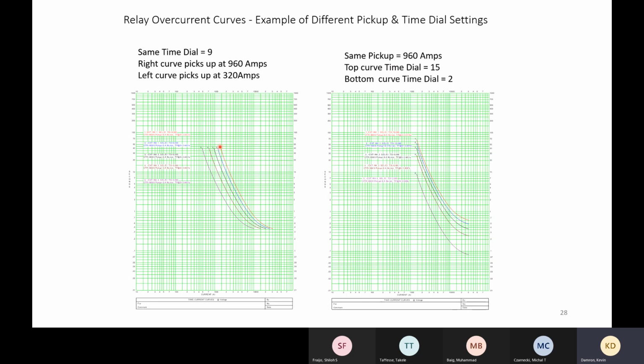And the reason they do that is, again, this is an electromechanical device. So the manufacturer only guarantees that it's going to operate at about 120 to 125% of pickup before that disc could start turning, but they're not going to guarantee that it's going to operate at a specific time. So even though curve 1 actually goes all the way up to 960, it really starts over here closer to almost 1500. So it's anywhere from about 1.25 to 1.5 where they actually start the curves. That's only for electromechanicals. For microprocessors, I can promise you at 101% it will start because it's mathematical. It's not an electromagnetic device. As long as your CTs are accurately measuring, then the device will operate at 100%. It'll be slow, and you're going to be up here in hundreds of seconds, but it will operate.